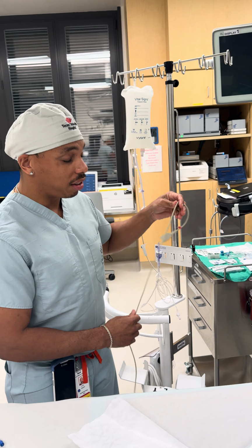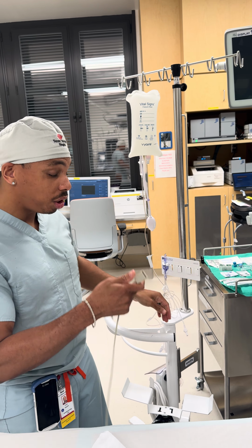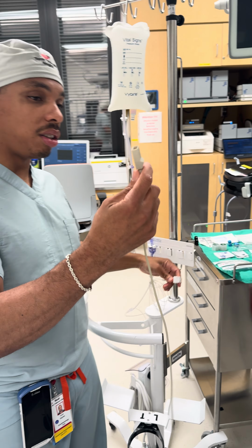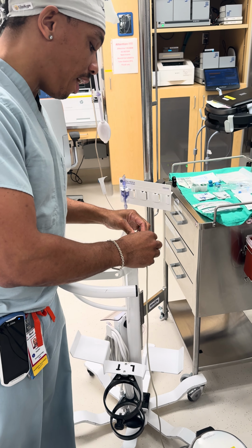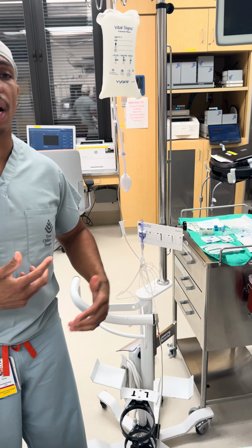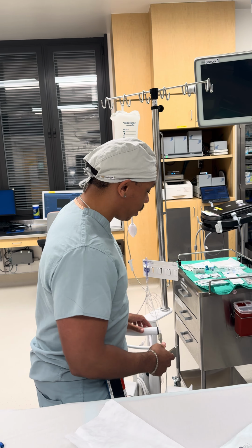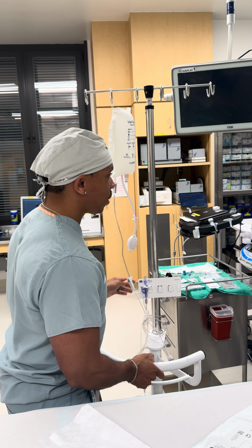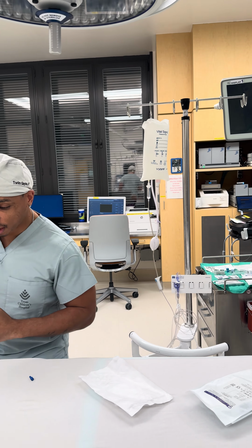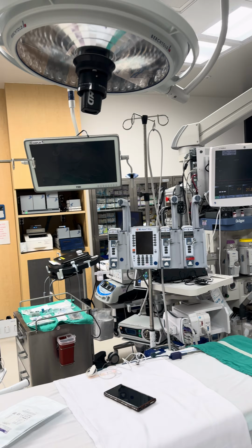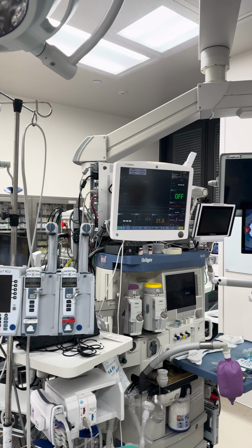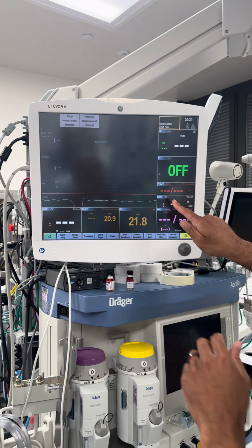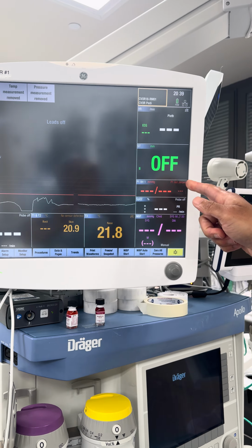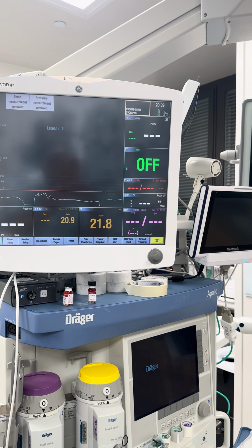So it's gonna come with the monitoring cable like so. What you wanna do is connect the transducer to the pressure monitoring cable. Now, it's important also to note that every institution is gonna have a different monitor, so it's not gonna look the same. However, the process of zeroing is always going to remain the same. So with that being said, I'm gonna come around here to my actual anesthesia monitor. And what you're going to see is this wave right here. You're gonna see arterial line pop up. It says not zero. And how do we zero it? Well, I'm gonna show you right now.